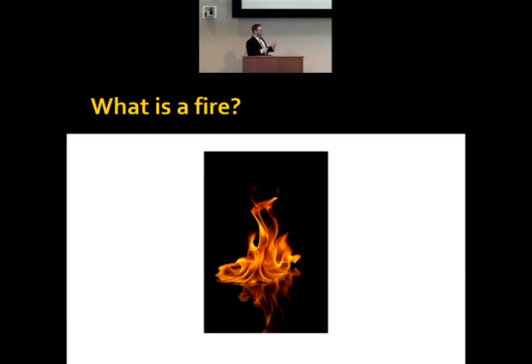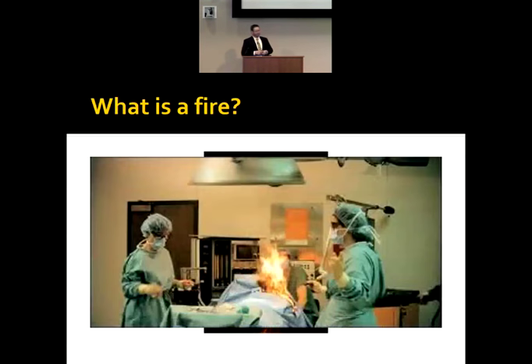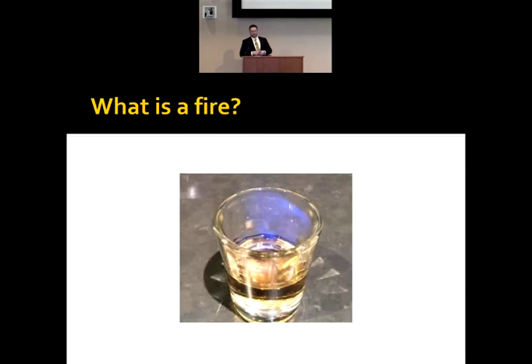So this is kind of what I pictured when I first thought about operating room fires. And then I just moved that into more of a surgical setting, so some nice blue towels. Maybe I'm activating the energy device and whoosh, this little flame comes up. Maybe it expands, maybe there's yelling and screaming, fire, and whatnot. But most of our fires these days are alcohol-based fires. They're this nice almost hard to see blue flame.